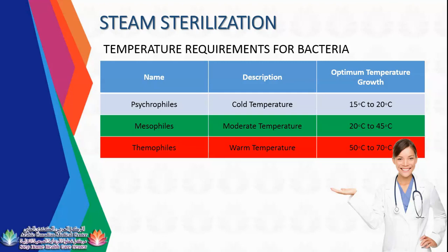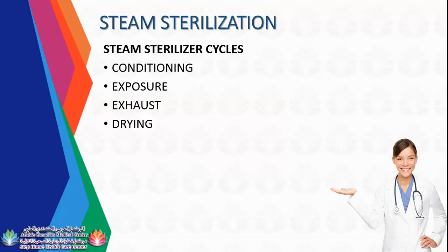I already discussed the cycles in the steam sterilizer, which are conditioning or preheating. The machine will preheat, then exposure, which is 3.5 minutes to 5 minutes, it depends. The exposure will start once it reaches 121 to 135 degrees Celsius. Exhaust means all steam generated in the chamber will be removed or evacuated.